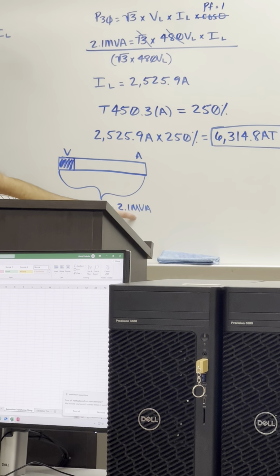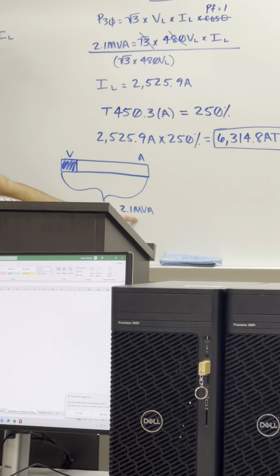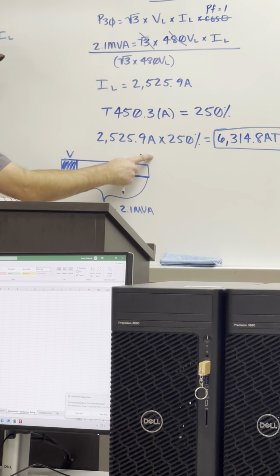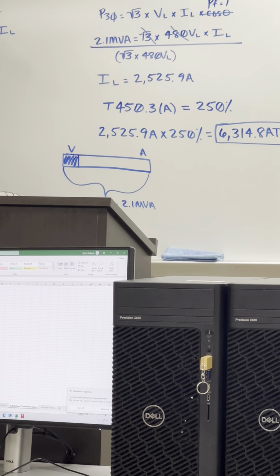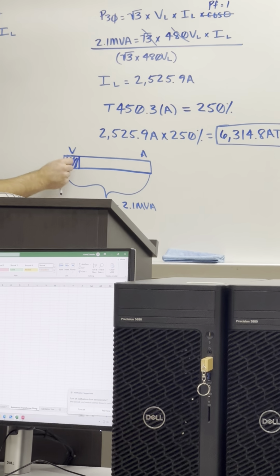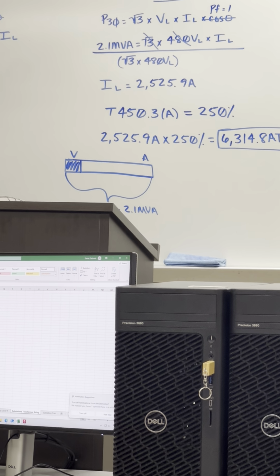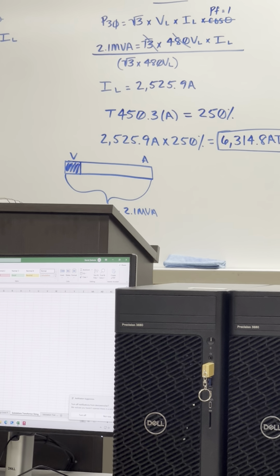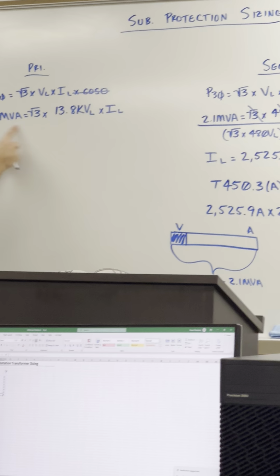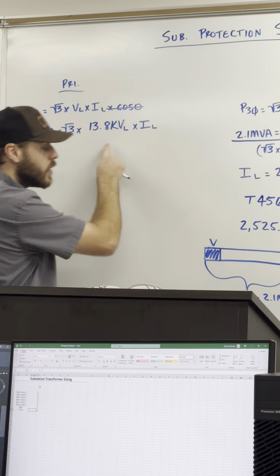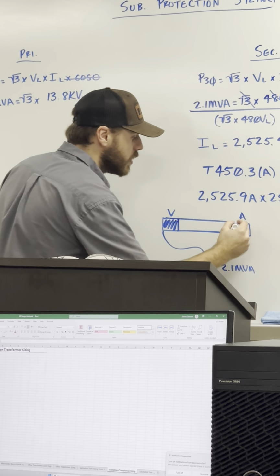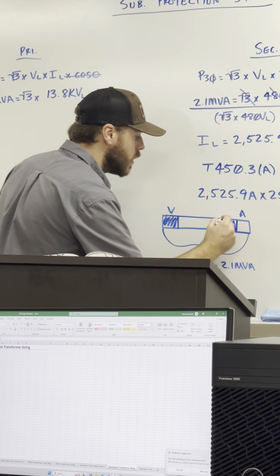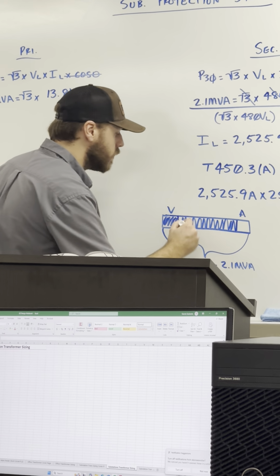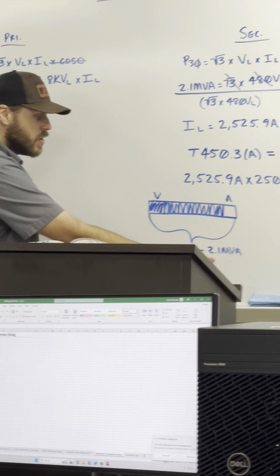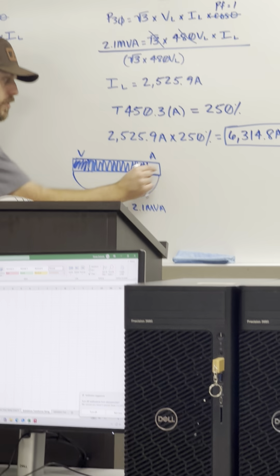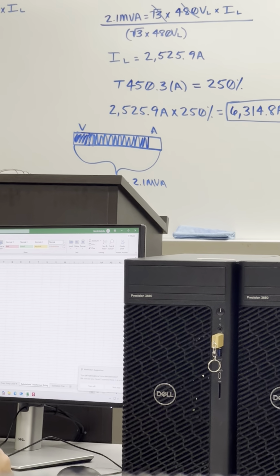Well, in order to calculate that value as far as our math goes, the volts and the amps need to come together to make that value. So we have such little volts that current is having to pick up the slack there. Well, when we come over here to the primary side, that 2.1 is not changing, but we're increasing our voltage. So if we greatly increase our voltage from 480 to now almost 14,000 volts, to maintain this 2.1 MVA, current has to shrink way down, right?